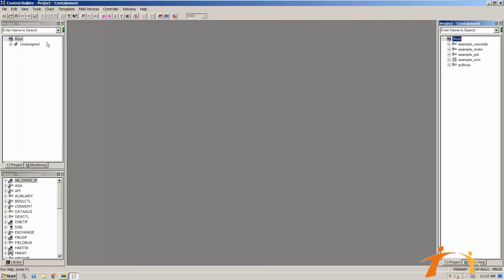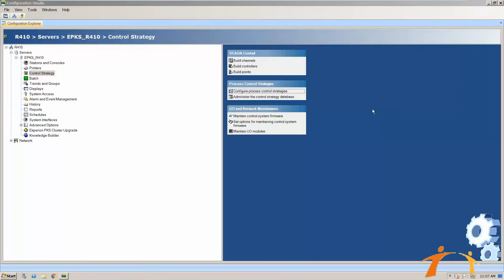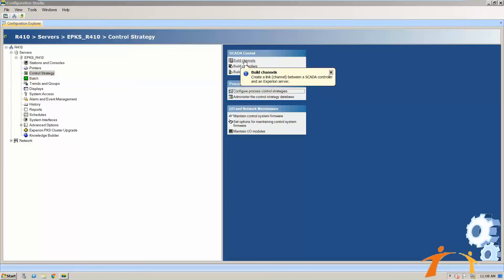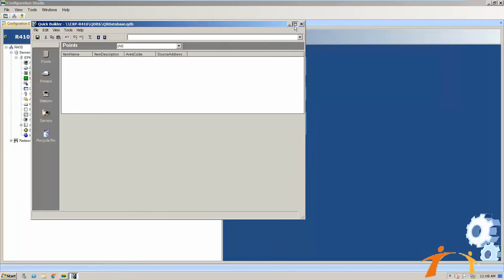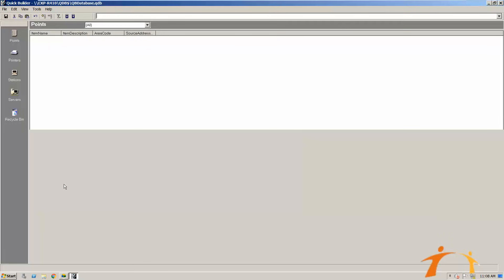Now let me show you where you configure SCADA. Within the same Control Strategy section you will find SCADA controls where you can build channels, controllers, and points. Click on any one of those and it will open the main software called Quick Builder. Quick Builder is where you connect your third-party systems, Honeywell-related systems, safety manager, and all those things. You can configure all the points, channels, and everything, then download it to run on your server.